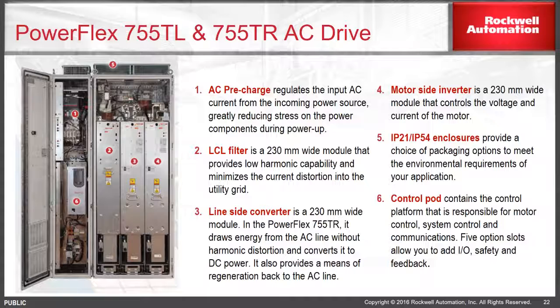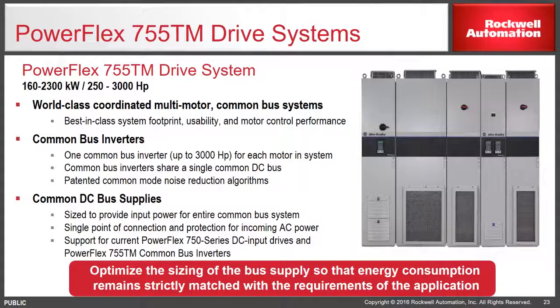The PowerFlex 755TM has a horsepower range of 250 to 3,000 total horsepower. It's a world-class coordinated multi-motor common bus system with best-in-class system footprint, usability, and motor control performance. It uses common bus inverters, one common inverter, up to 3,000 horsepower for each motor in the system. There's a common bus that feeds all the inverters. There's common mode noise reduction.